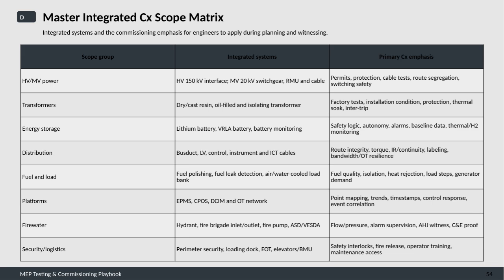Fuel and load systems include fuel polishing, leak detection, and load banks cooled by air or water. The commissioning emphasizes validating fuel quality, isolation mechanisms, heat rejection processes, load step operations, and generator demand controls.